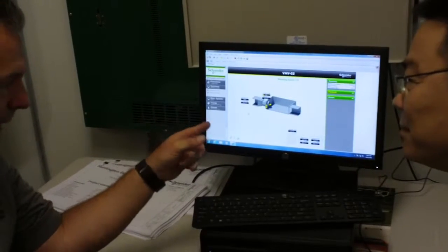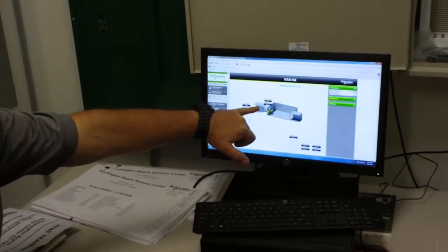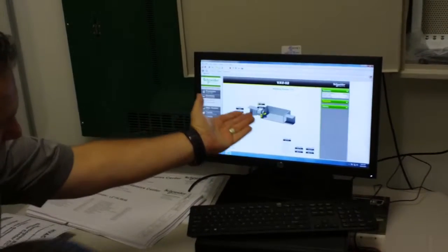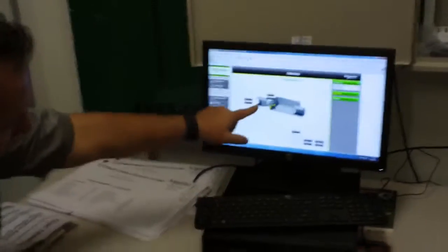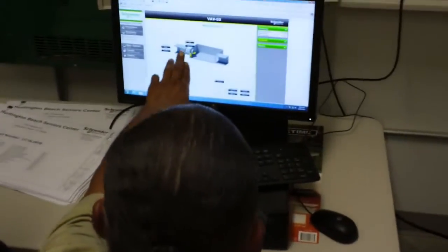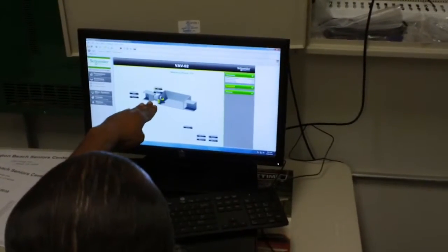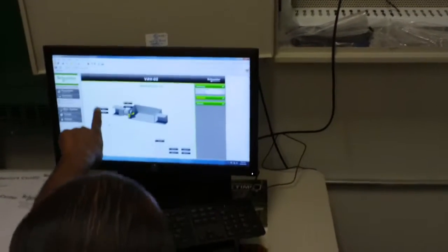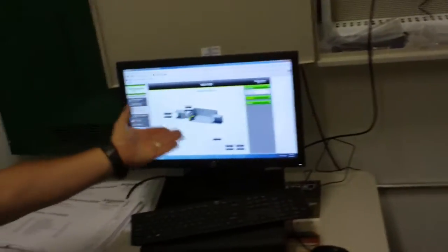So you guys are doing an air balance, so we may see different readings on here? It's already been locked in. Say, for instance, if this is roaring out right now, we're doing an air balance where maybe the damper position is like 80%? We won't air balance from an actuator. What we do during air balance, this is 100% open, and we have a manual volume damper. This is supply air, right? We have a manual volume damper sitting over here that we balance off of. So you would just have this at 100% or 99% open. Correct, so controlling the flow.